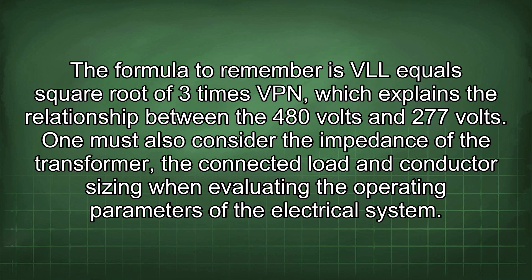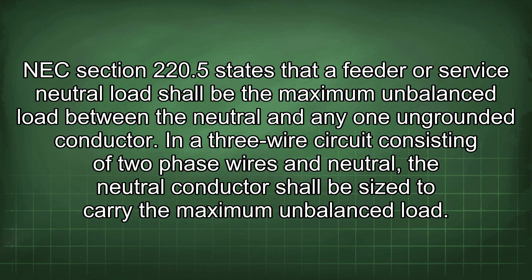One must also consider the impedance of the transformer, the connected load, and conductor sizing when evaluating the operating parameters of the electrical system. NEC section 220.5 states that a feeder or service neutral load shall be the maximum unbalanced load between the neutral and any one ungrounded conductor. In a 3-wire circuit consisting of two phase wires and neutral, the neutral conductor shall be sized to carry the maximum unbalanced load.